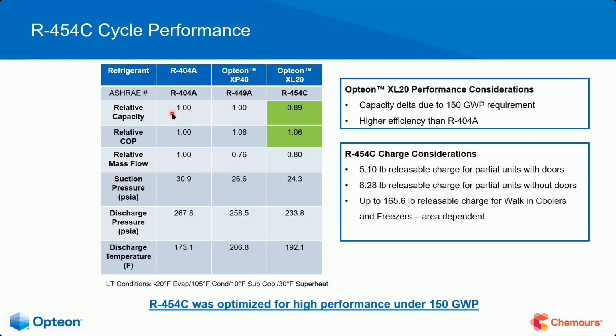So here our baseline is 1. 449A didn't change, obviously. It's going to stay the same. So if you're retrofitting that, it's a very easy retrofit, by the way. And on the new equipment, you're going to lose a little bit of capacity, down to 0.89. But hold the phone. When it comes to relative COP, which is, in my opinion, the biggest and most important number on here, we're going to have 1 here. You're going to gain again 1.06 on 449A, and you're also going to gain 1.06 on the new equipment.